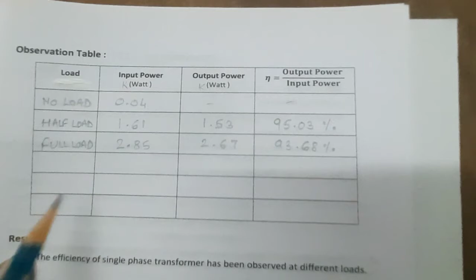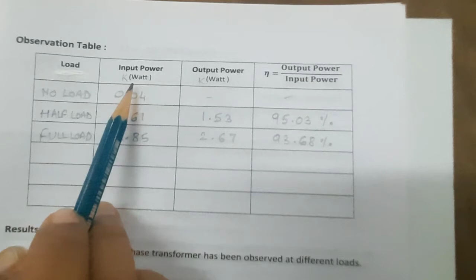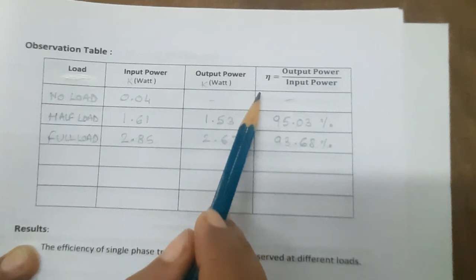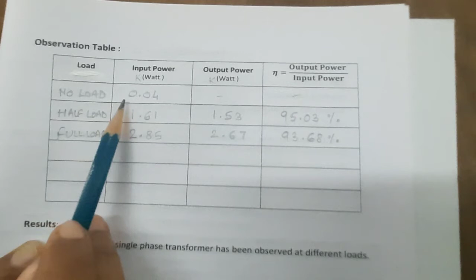So this is the observation table. The first column is the load, whether no load, half load or full load. The second is the input power at the primary side, then the output power at the secondary side, and the efficiency, that is the ratio of output by input. First we took the reading at no load, where the input power was 0.04 kilowatts.